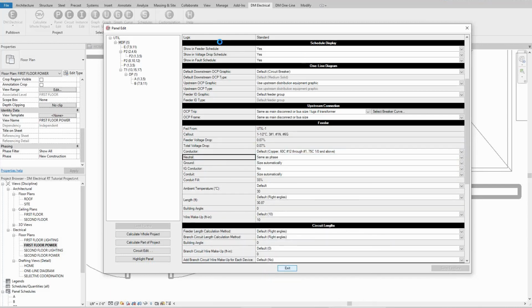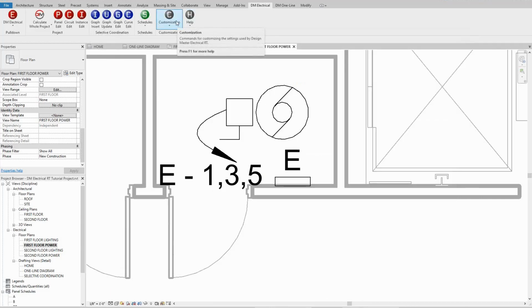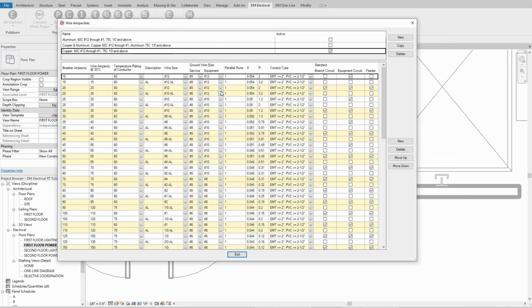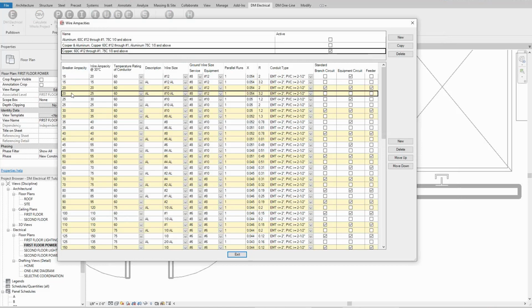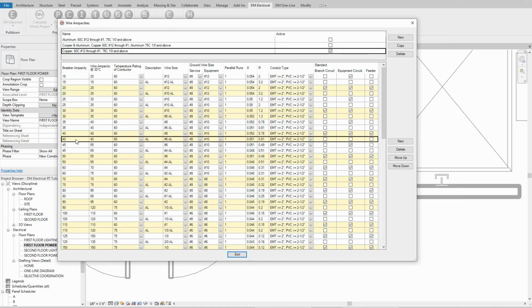For the wire sizing, we've also added the wire ampacity separate from the breaker ampacity. So all of the wire sizing happens here in terms of choosing what size wire to use for what size circuit. Previously, we had just the breaker ampacity being listed. So the software, you'd get a breaker size, and then we would size the wires based upon that. And that's still how it works. So for a 40 amp breaker, you're going to get either a number 8 copper wire or a number 6 aluminum, depending on which sizing method you're using.